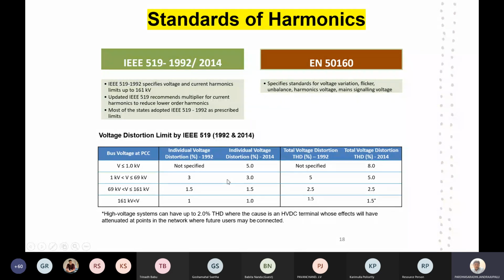So here, the percentage of voltage distortion: if V is less than 1 kV, maybe three-phase or single phase, in India, the individual voltage distortion should be 5%. Whereas for THD, they are expecting 8%, that is total voltage distortion. That is, in voltage, harmonic distortion of 8% is accepted.